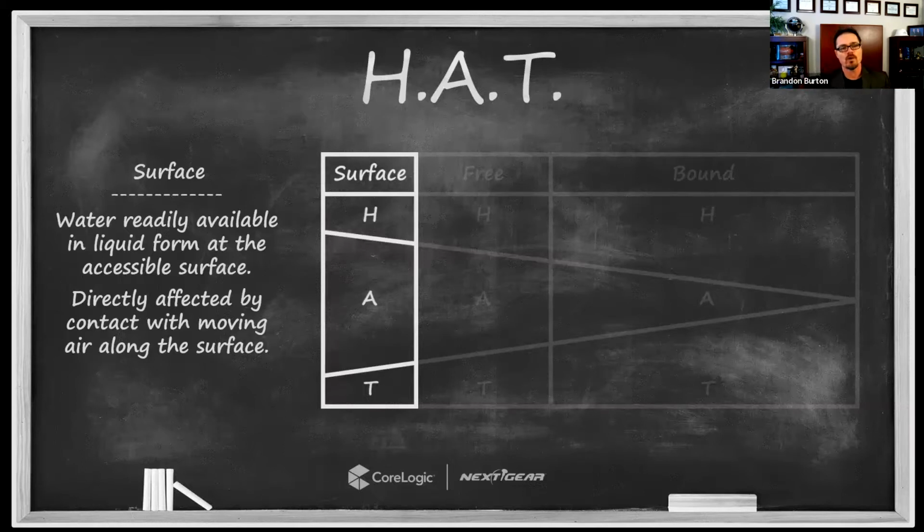And this is the reason why we generally set as a goal, just keep the relative humidity below 60% initially. Just keep it there so we don't get secondary damage. But we don't need an extremely low humidity initially. We just need tons and tons of airflow.